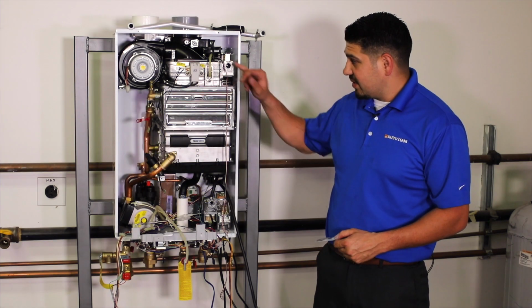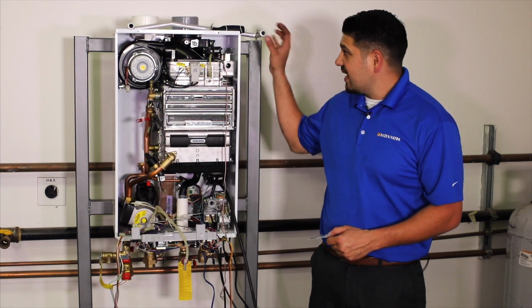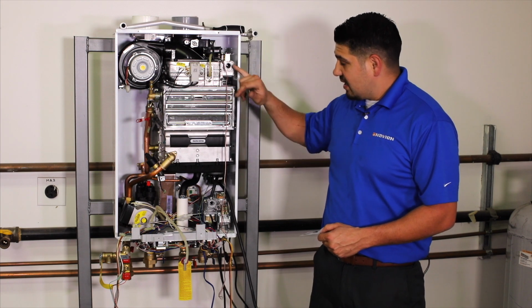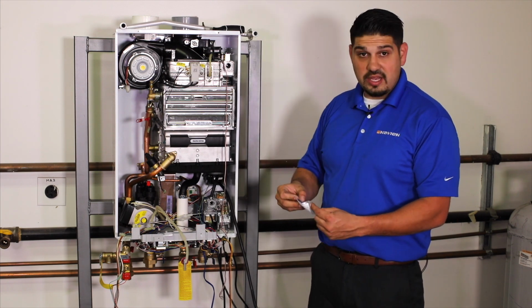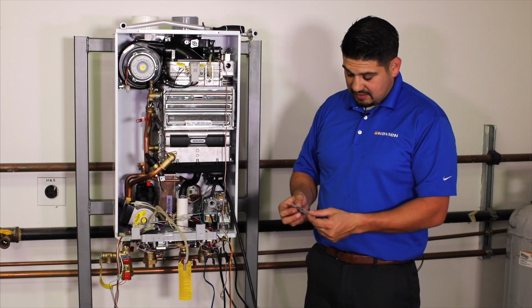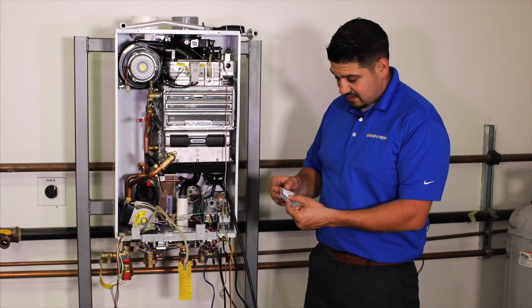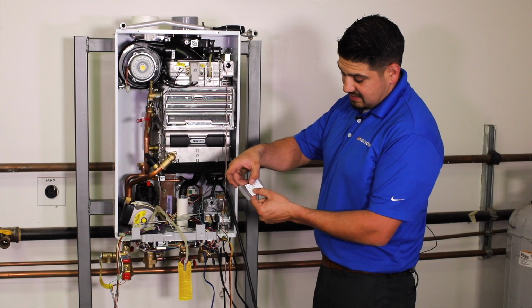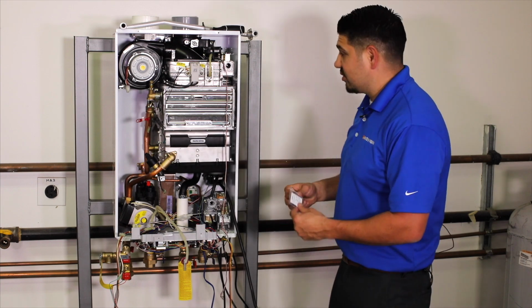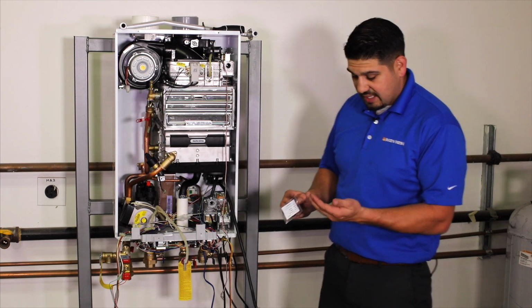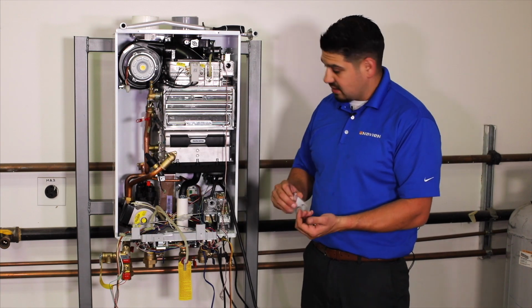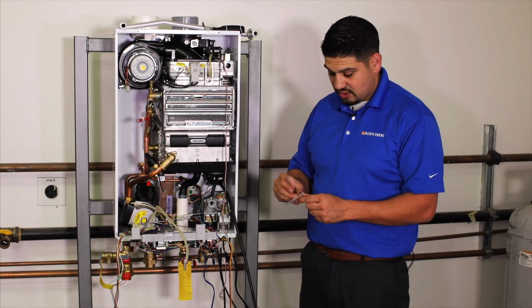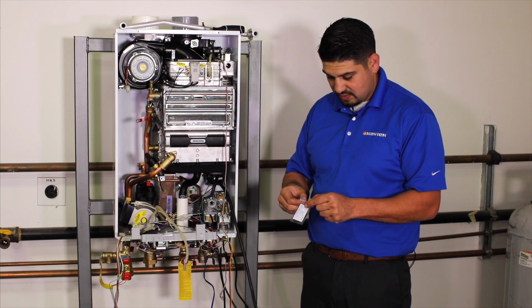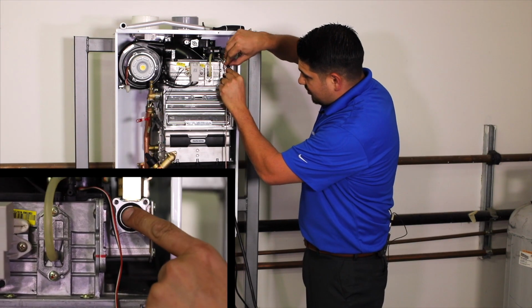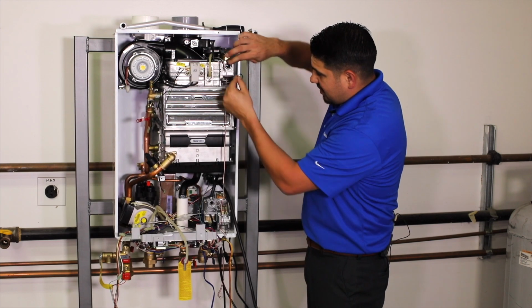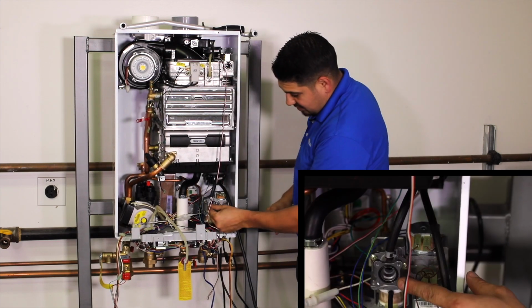We're going to start working on the combustion side of things. We have our gas tube, which is right here. And in our new heat exchanger replacement kit, we got these new gaskets or O-rings, and it just says gas pipe O-ring, so we know which ones we're dealing with. Also in our hardware kit, it gave us new screws for our gas line, so we're going to go ahead and change those out to the new ones.